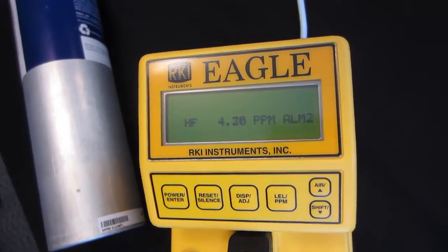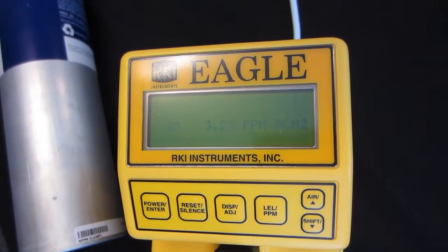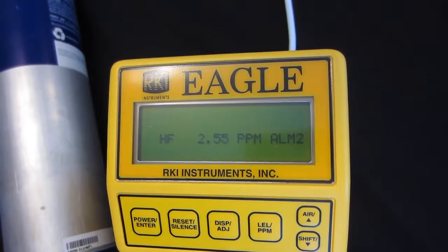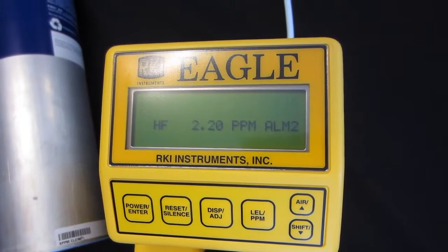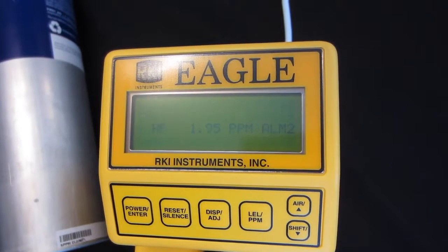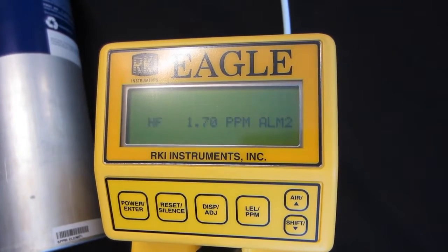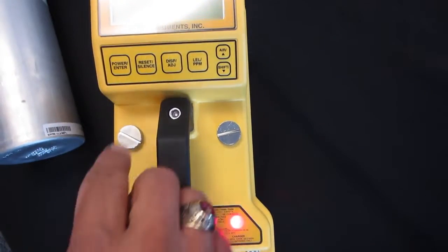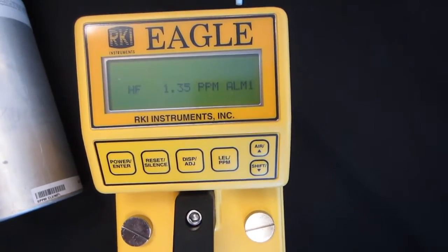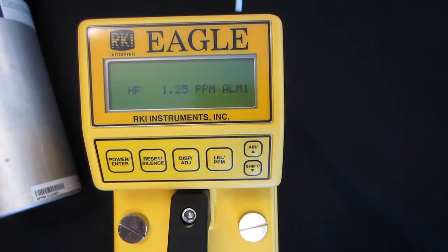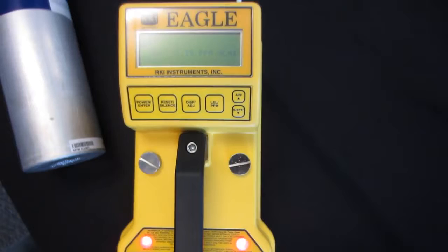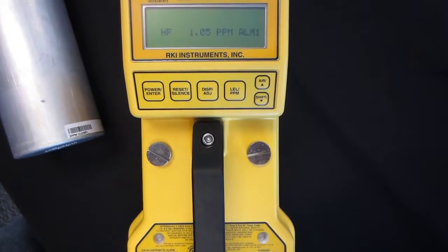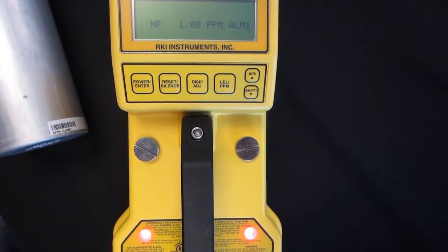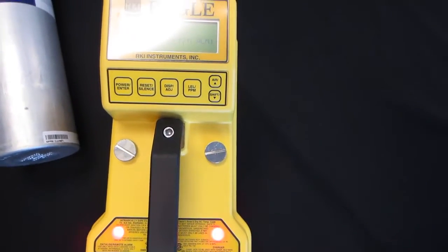And now we're just going to wait for the reading to start dropping. So again, we achieved the calibration value on our bump test in about a minute and a half, roughly. And when the reading drops below the alarm points, you will be able to silence them by pressing the reset silence button. Okay, so right now I was able to silence the buzzer, but the LEDs are still flashing. That means I'm between the low alarm and the high alarm points when I press that reset button. Once the reading drops below the low alarm point, I'll be able to press the reset button again, and that will turn off the LEDs.